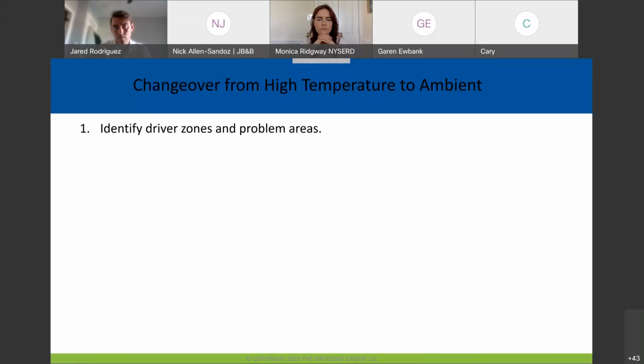But in the case of driver buildings and driver zones, for example, a gymnasium might be a driver for both outside air and air conditioning for a rec center. It in turn needs maybe 41-degree chilled water to air condition it adequately, but the other zones in that building would only require 50-degree water. What could we do? Well, by identifying it as a driver zone, it lets us isolate that and maybe put a different piece of equipment there, or a different way that we distribute, so that we can get more energy out of it.